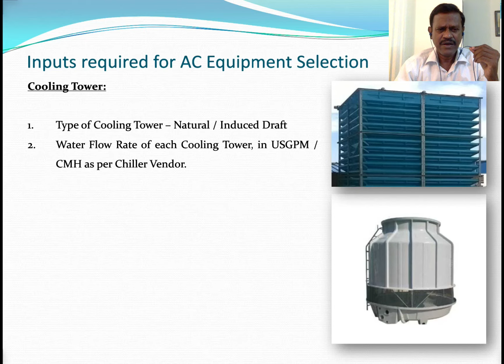Next is condenser water temperature, what temperature you want at the cooling tower outlet, that you have to specify based on the chiller vendor. See, what I am trying to say is, if the chiller is selected for 30 degrees centigrade condenser water inlet temperature, then your cooling tower outlet should be 30 degrees. Or if the chiller is selected for 32, then you can ask for 32 degree outlet. So that is the meaning of that.